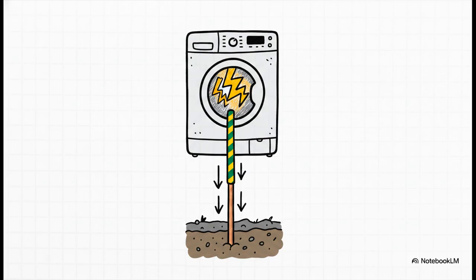power instantly. And depending on how your specific home is set up, that earth path is carried safely away to the ground via a connection to the service neutral, the metal sheath of the underground cable, or maybe even a direct copper electrode rod that's literally driven into the earth right outside your house.